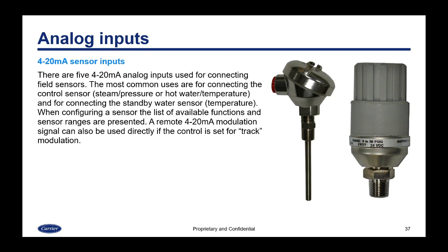There are 5 4 to 20 milliamp analog inputs used for connecting the field sensors. The most common uses are for connecting the control sensor, which is going to be your steam pressure or hot water temperature sensor for controlling the process, as well as for connecting the standby water sensor on a steam boiler. When configuring a sensor, the list of available functions and sensor ranges are presented on the screen for you. A remote 4 to 20 milliamp modulation signal can also be used directly if the control is set for track modulation.